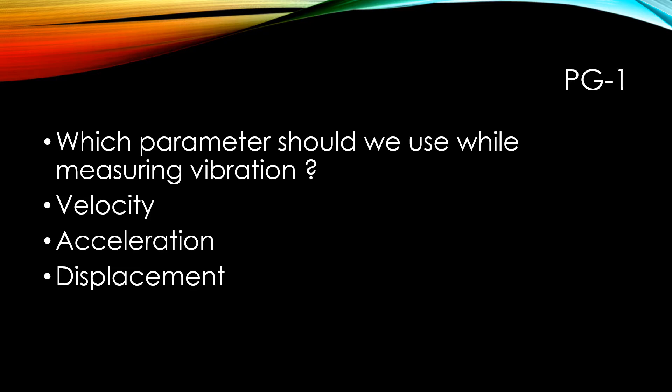Generally in the case between 10 Hertz to 1000 Hertz, the velocity gives a good indication of the severity of vibration. The majority of the general rotating machineries operate between 10 to 1000 Hertz range. So velocity is the most common vibration measurement and analysis tool.